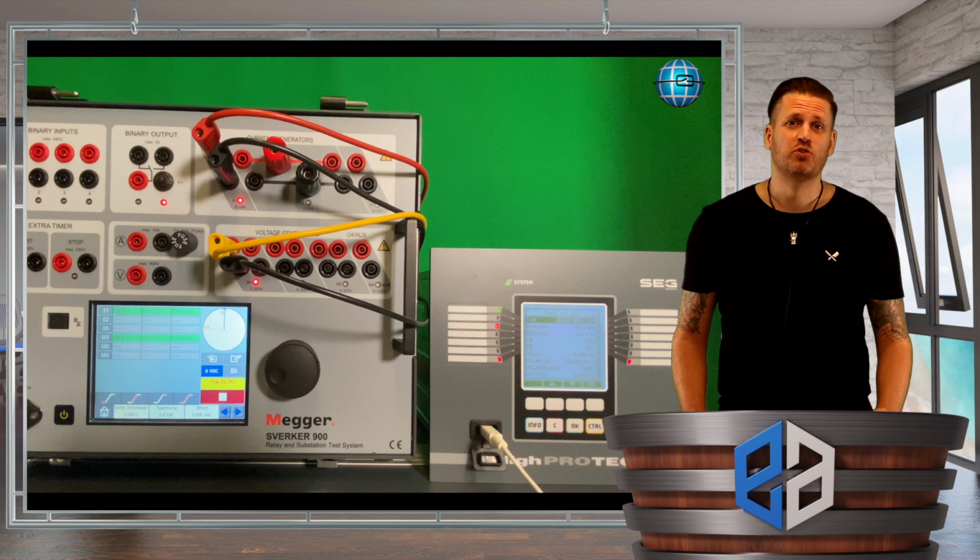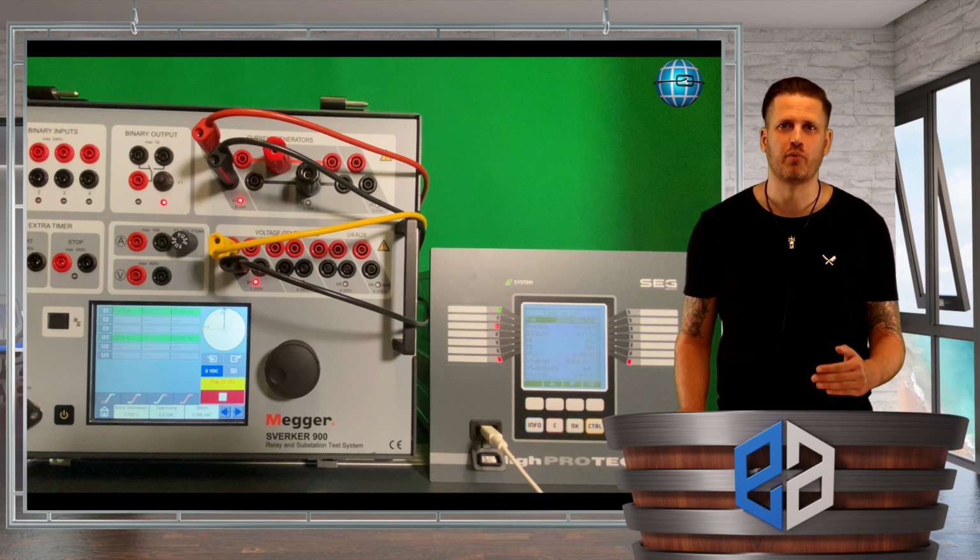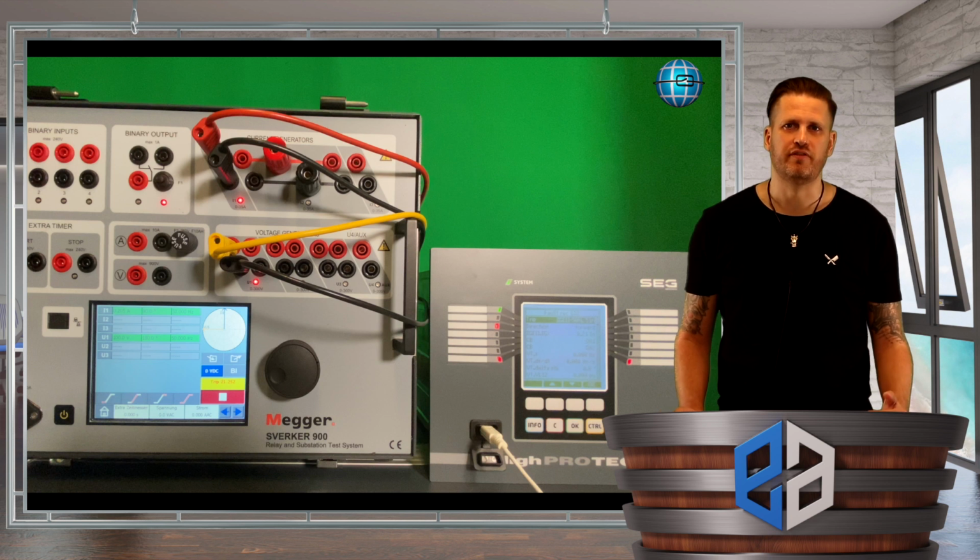Great! We are now doing an analog ramp test for the voltage pickup. This time we keep the current value constant over the pickup range. The implementation is very easy and we won't repeat it now.